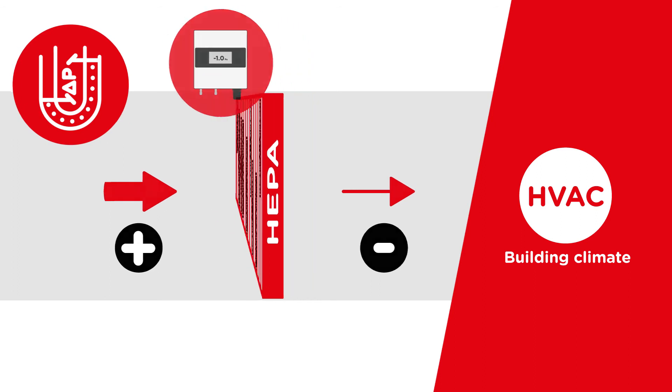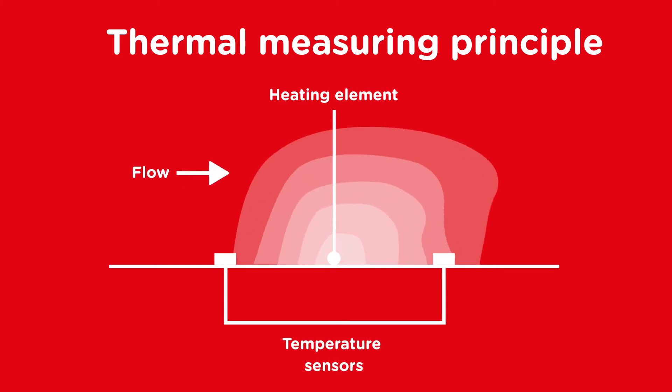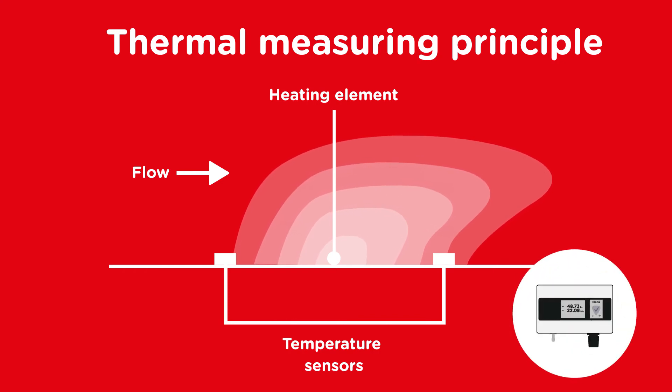There are two main principles for measuring differential pressure. In the thermal mass flow principle, two temperature sensors are used. The airflow affects the temperature profile, which is detected by the sensors and evaluated by the electronics. This effect is measured and evaluated.